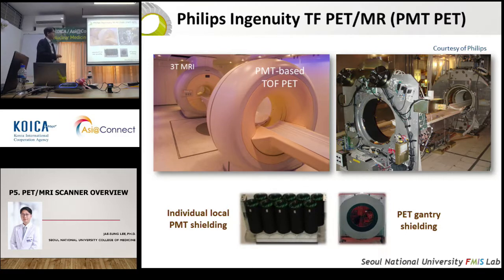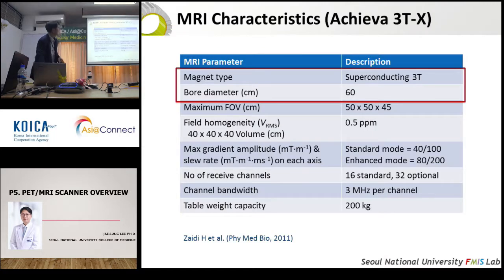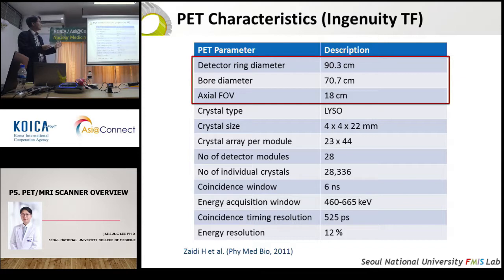So this is why, in the Philips system, in which they use photomultiplier tubes for the sequential PET MR, the PMT based time of flight PET is much separated from the 3 Tesla MRI to minimize that kind of interference. They shielded the photomultiplier tubes like that, and they also applied some gantry shielding to minimize the interference between them.